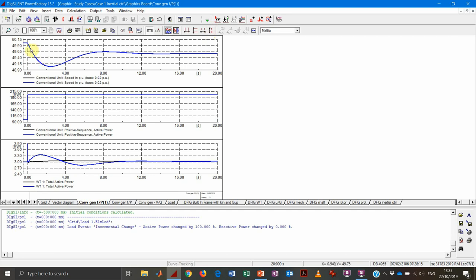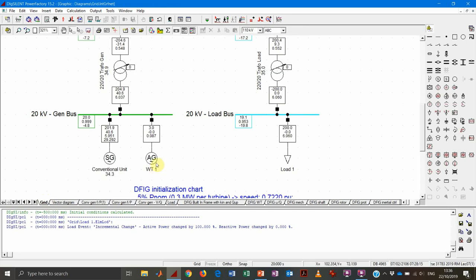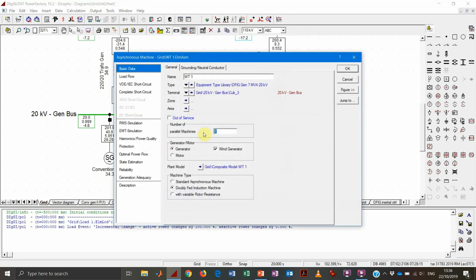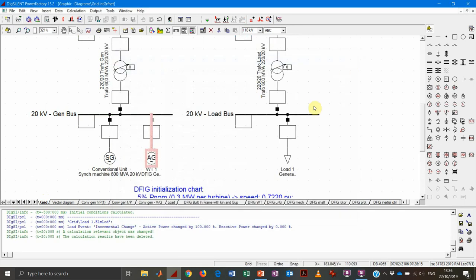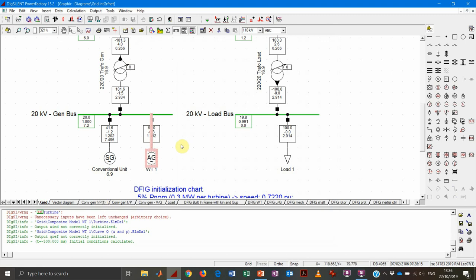We can also see that we are not affecting the frequency dynamic that much. We need to be aware that we have one wind turbine of 7 megavolt-ampere versus a conventional unit of 600 megawatts, so it's an unfair comparison. To make it more interesting, we can put more machines in parallel — let's say 20 machines. All 20 machines will behave exactly the same way. What PowerFactory does is get the dynamic of the individual machine and multiply the various outputs by 20.